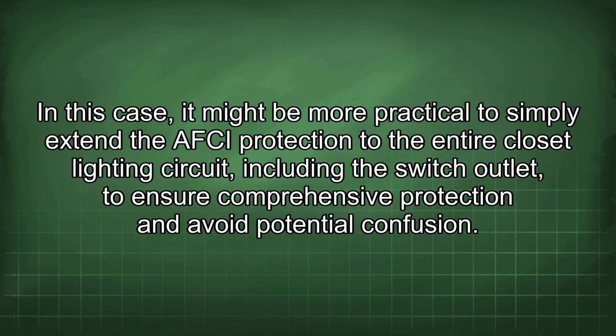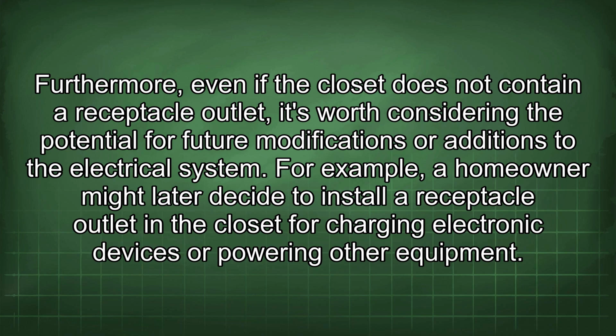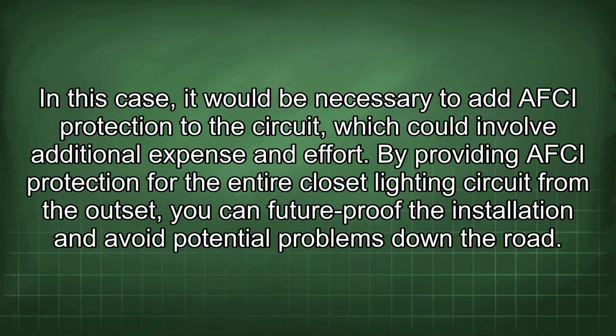In this case, it might be more practical to simply extend the AFCI protection to the entire closet lighting circuit, including the switch outlets, to ensure comprehensive protection and avoid potential confusion. Furthermore, even if the closet does not contain a receptacle outlet, it's worth considering the potential for future modifications or additions to the electrical system. For example, a homeowner might later decide to install a receptacle outlet in the closet for charging electronic devices or powering other equipment. In this case, it would be necessary to add AFCI protection to the circuit, which could involve additional expense and effort. By providing AFCI protection for the entire closet lighting circuit from the outset, you can future-proof the installation and avoid potential problems down the road.